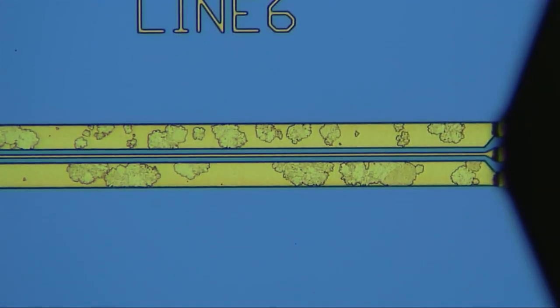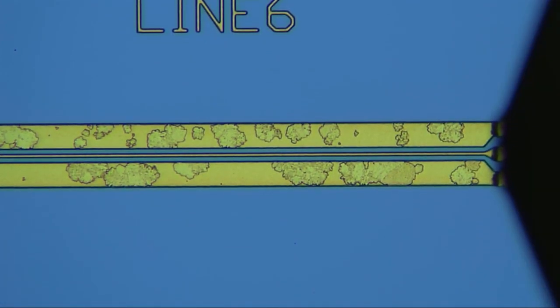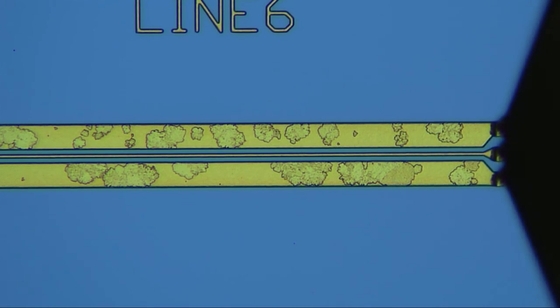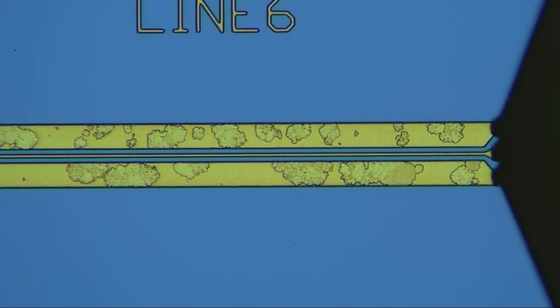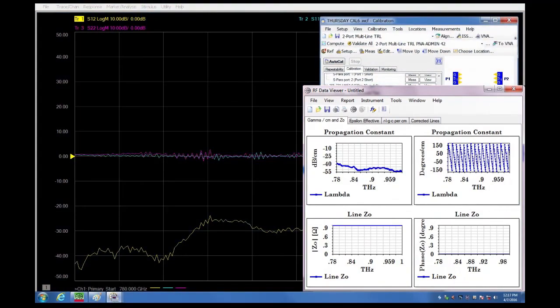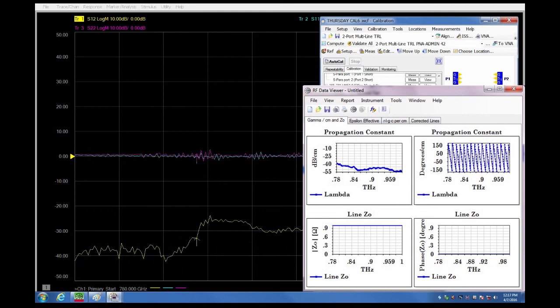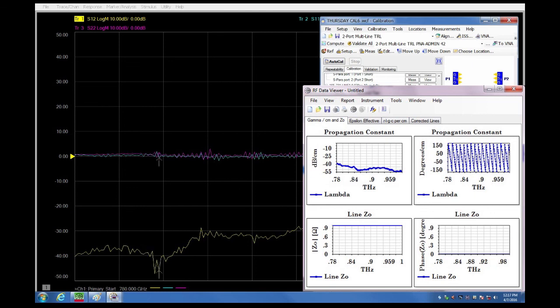And we move. And here's our last measurement. At the end of the cal, we'll get WinCal to compute the error terms. And in doing so, it also calculates other factors such as the propagation constant. As you can see here, which looks fairly nice and flat with a very regular propagation constant in terms of phase also. This concludes the calibration.